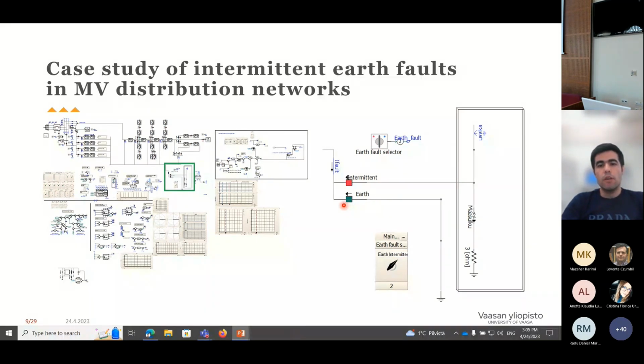For the earth fault, which is a permanent one, we have this path, and for the intermittent one, which is an intermittent connection of a conductor to the earth, we modeled a random signal to make the circuit breaker switch on and off. But in the future, we will use real data to be sure about the exact pattern. As well as this, we are using different resistors because of the semi-sporadic and unpredictable nature of such faults, to be exact in this situation.